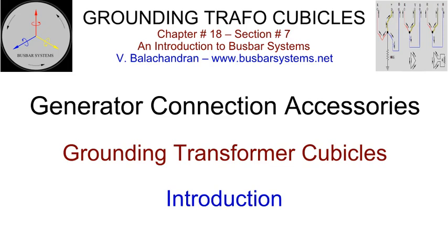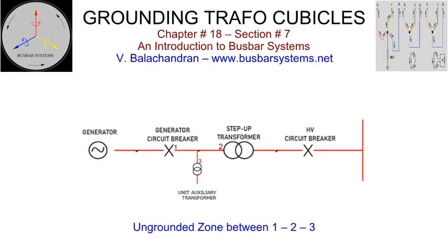Introduction. In large power stations, the generators are connected to the generator transformer by an isolated phase bus. A generator circuit breaker may be installed between the generator and the generator transformer based on economic consideration or ease of operation. In captive power plants with smaller unit sizes, the generators can be connected directly to a circuit breaker of a distribution board.